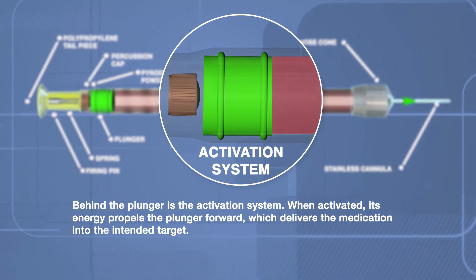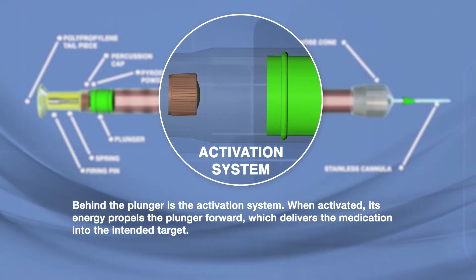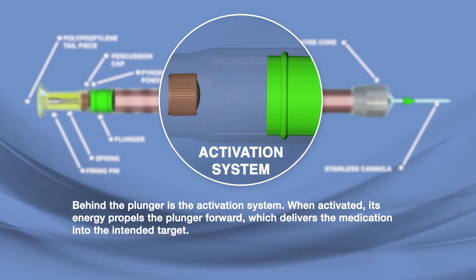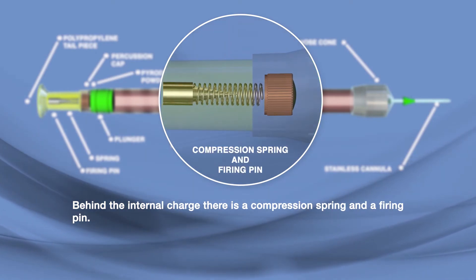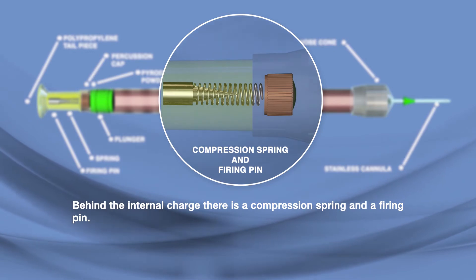When activated, its energy propels the plunger forward, which delivers the medication into the intended target. Behind the internal charge, there is a compression spring and a firing pin. The spring positioned in front of the firing pin is there to prevent premature activation while in transport.